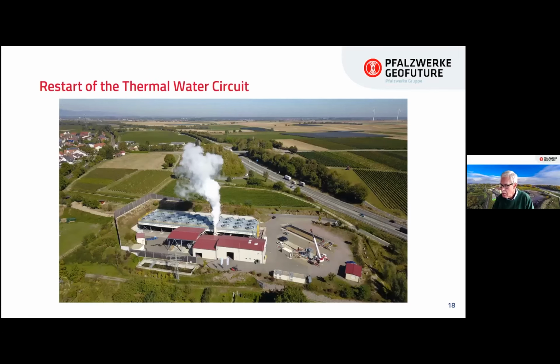When restarting the power plant, we have to heat up the whole brine system, especially the production pump in our well. For a limited period, over about one day, we operate the brine circuit through a separator, producing a steam phase above our power plant. It's always quite tricky to adjust the driving shaft of the production well pump — since it's 750 meters long, it extends as it heats up, so it has to be readjusted 2 or 3 times during the restart procedure.